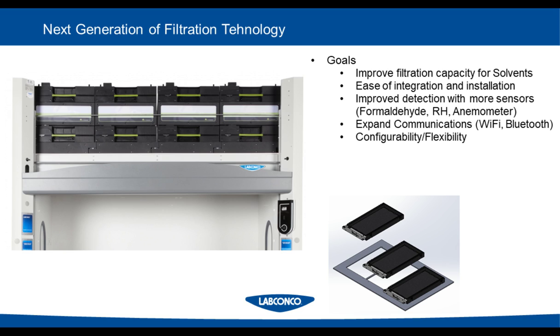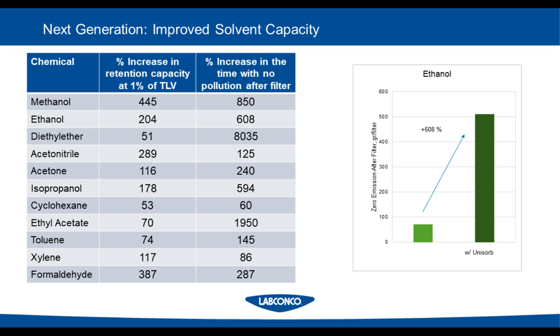And then the configuration and flexibility: there are different pre-filters you can use along with different sensors you can use depending on your specific application. But as Kasey had also mentioned earlier, there's that one filter type that handles acids, bases, and solvents simultaneously, in much higher volumes than in the past, and simplified the maintenance also, of course. With these improvements now it's much easier to maintain these hoods. It was pretty easy before, but it's a lot easier even now.